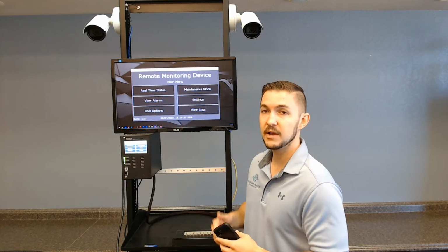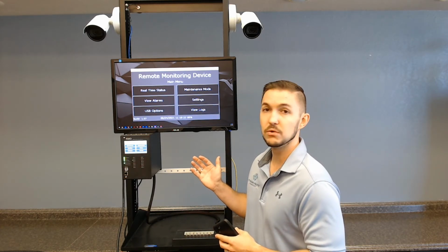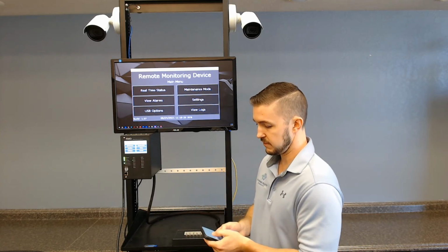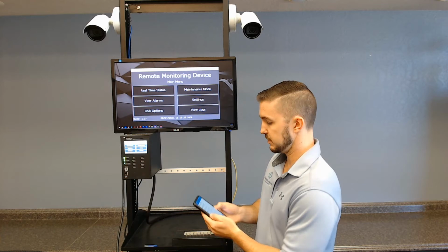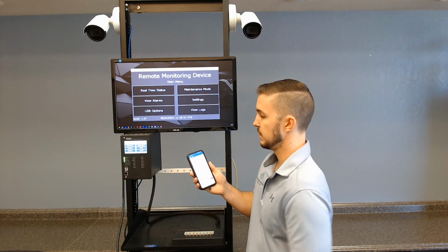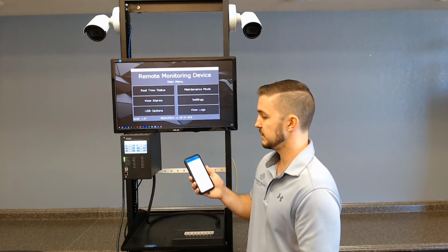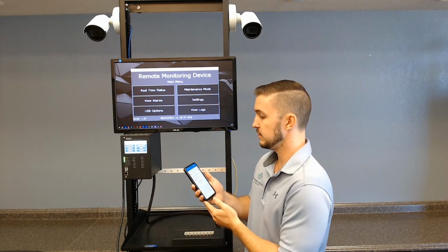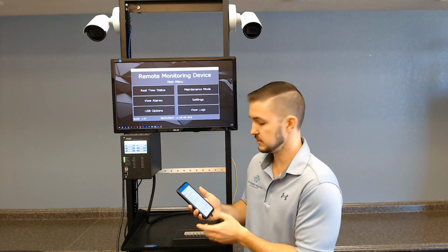We'll restore commercial power, and this particular alarm is set to re-alert as well on recovery. So now whenever I come and refresh on my phone here, I should expect to see two alerts, one being commercial power has been out for more than 10 seconds, and then I get the other one saying it recovered and the alarm was active for 17 seconds.